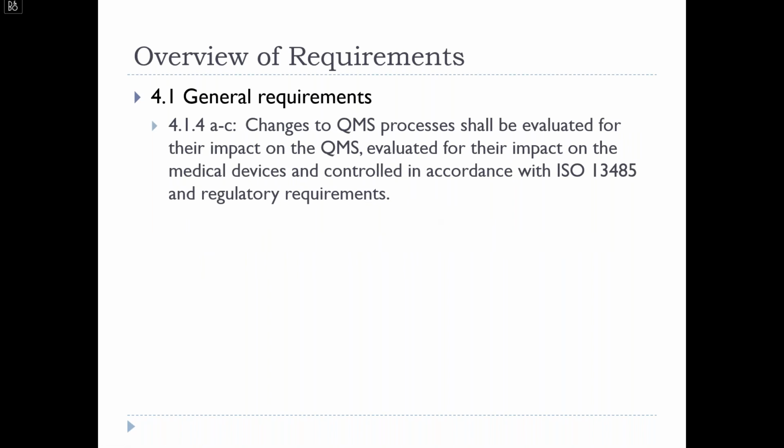4.1.4 says that changes to processes shall be evaluated for their impact on the management system, as well as their impact on the medical device, and controlled in accordance with 13485 and regulatory requirements. So you need to understand what regulatory requirements are applicable.